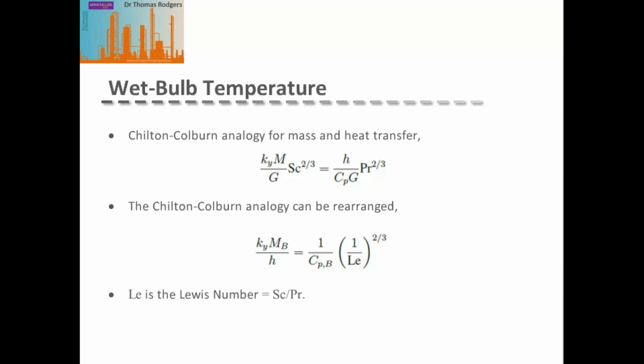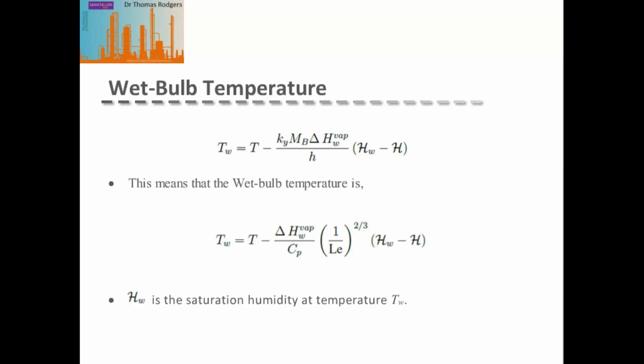The Lewis number is the ratio of the Schmidt number to the Prandtl number and can be looked up for a wide variety of systems. Substituting this expression into the wet bulb temperature relation gives the wet bulb temperature in terms of the convective gas temperature, the enthalpy of vaporization, the specific heat capacity, the Lewis number, and the difference between the saturation humidity at the wet bulb temperature and the humidity of the convective gas.